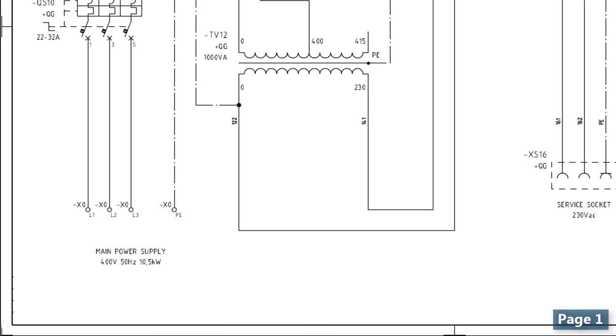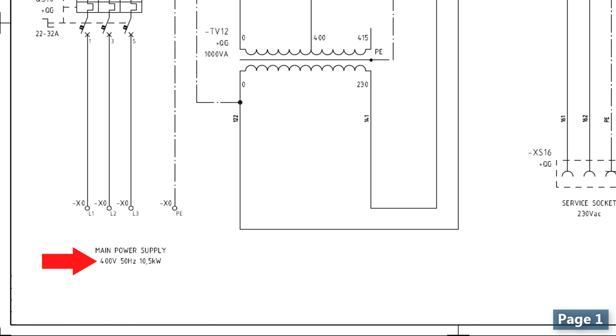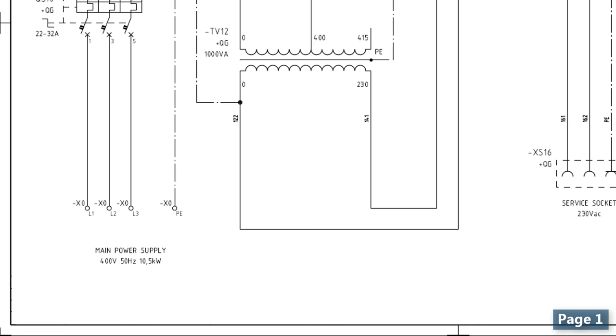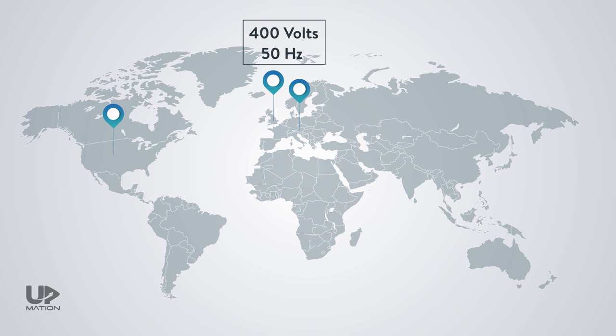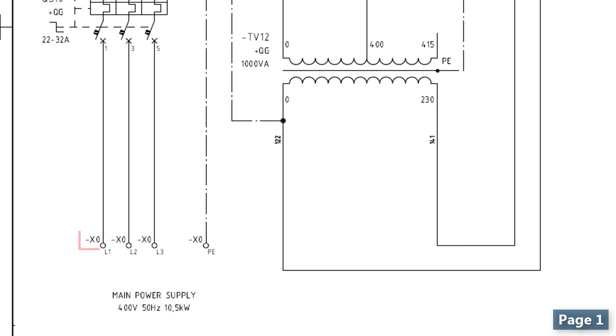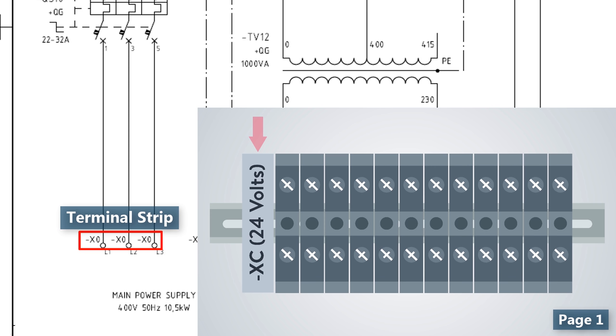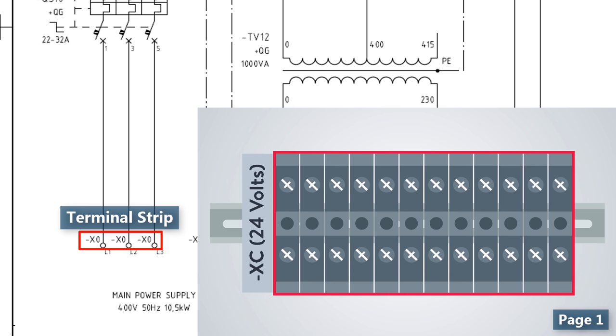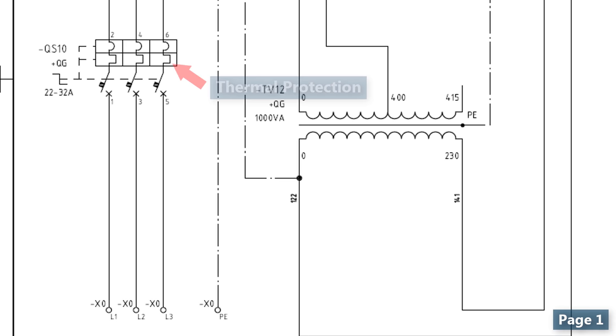So, as an exception, we should start from the downside and this is where the three-phase power enters the panel. As a reminder, the voltage level and the frequency of the power depends on the country we are implementing our project. For example, in England or Austria, the voltage level is 400V with 50Hz of frequency. But in the United States, a three-phase power source will produce 480V with 60Hz of frequency. As you see, the power enters the terminal blocks with the X0 terminal strip. The terminal strip is a mark that refers to a group of terminal blocks with the same voltage level or the same purpose.